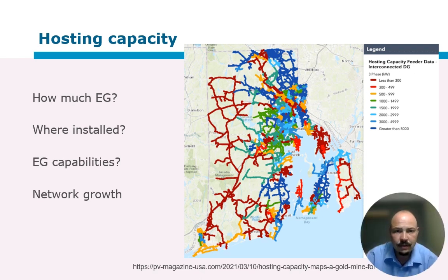Ideally, the distributor should do the hosting capacity analysis on a regular basis, so that at least the first evaluation can be done quickly and without significant resource requirements. This would be similar to the NRS 097-2-3, where simplified criteria can be determined per area of the network for ease of assessing and evaluating applications in step 2.